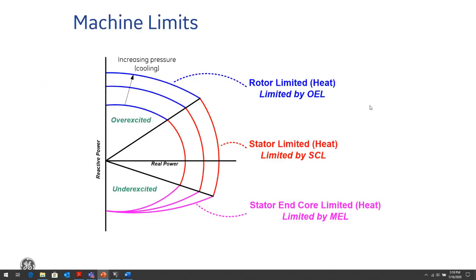When we talk about the generator, like any piece of equipment, there's a limit as to how we can operate the machine. Usually, the stator limit is what we're going to be mostly operating in, and that's where we're generating real power into the system, usually with some lagging or some leading power factor, so that we can supply VARs into the system to maintain the voltage stability of the system. And this generator capability curve defines the boundary within which it can deliver real and reactive power continuously without causing overheating or damage in the generator.